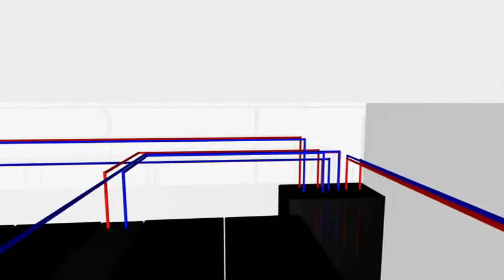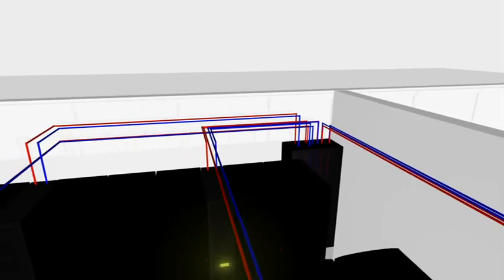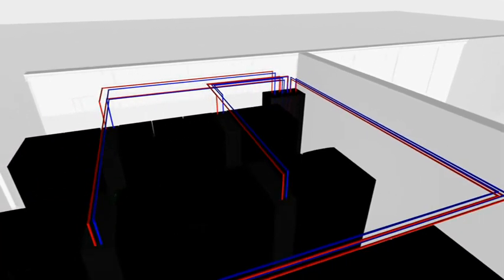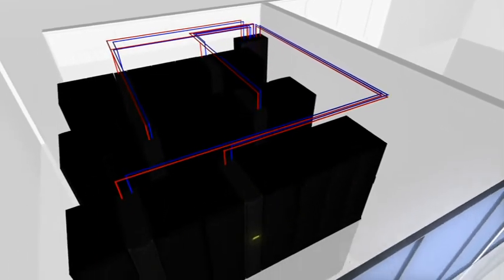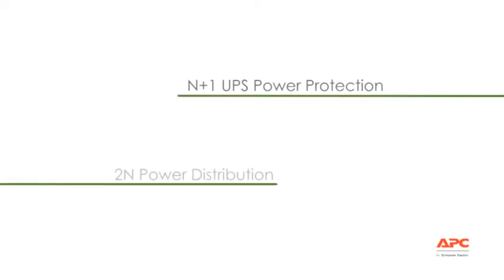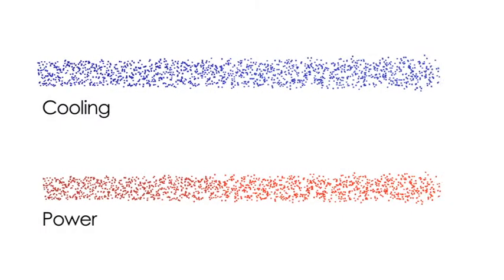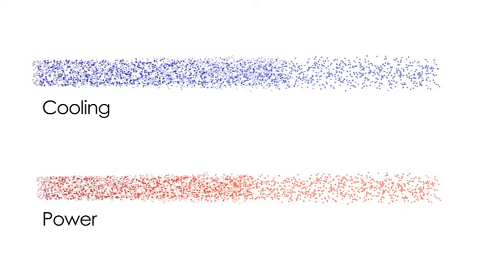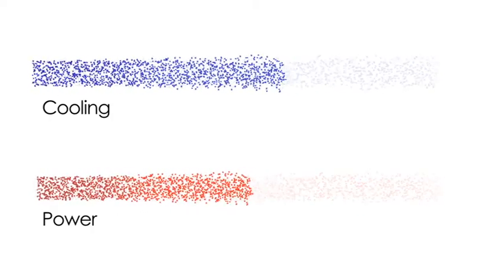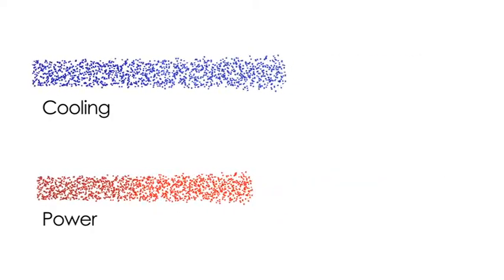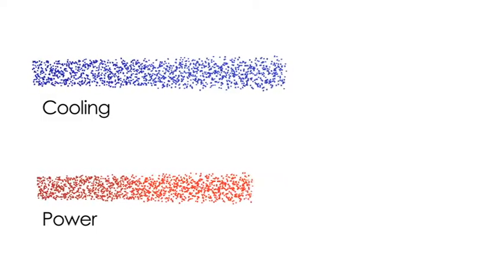The initial design phase and configuration to suit the business requirements of the TAFE has played a very important role. The data centre can now provide an N+1 on the power protection and a 2N on the distribution redundancy level. It is a very efficient system with savings up to 30% compared to similar data centres with a legacy designed power and cooling infrastructure.